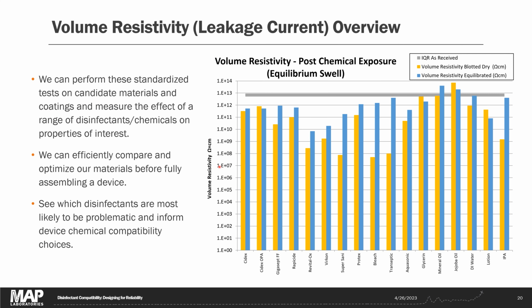So now we have a standardized test for component level electrical properties that we can use as we see fit. We can do a 1 hour exposure like I showed on the previous slide. We can do a standard 8-minute disinfectant usage, measure the electrical resistance, then do a rinse, see if the electrical resistance changes at all. Or we can do a worst case scenario, which is let the material sit in the disinfectant for several days until it's gone to equilibrium, and that'll give us an idea of what are the worst disinfectants. In the worst case scenario, somebody forgot the probe in the disinfectant over the weekend. What are the worst disinfectants that we need to worry about?